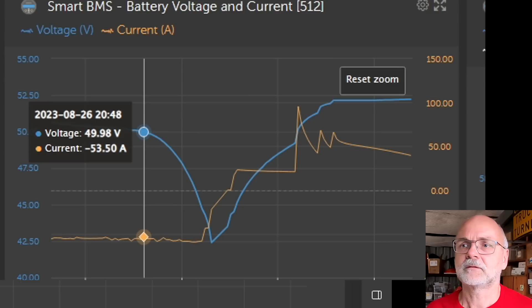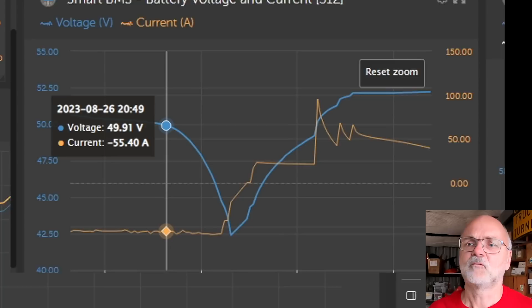From there it's going down from 52, 53 volts all the way down into the discharge knee. If I zoom into this part again, you can see at 50 volt, 48 volt, we've got around 30 millivolt deviation only, and then it goes down. At 48 volts, we've got like 80 to 90 millivolt deviation. This was the lowest we could get, 42.4 volts, and we had a deviation of around 300 millivolt.